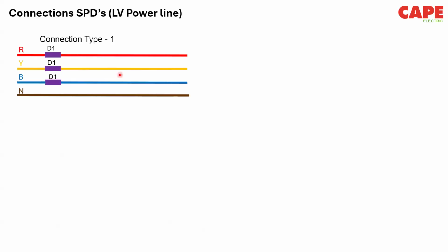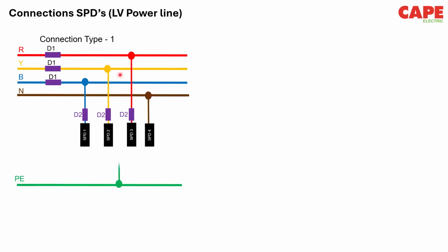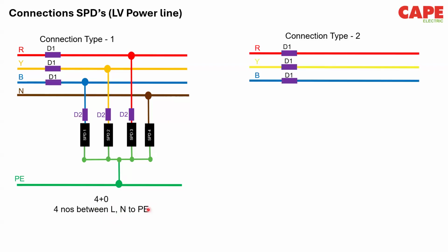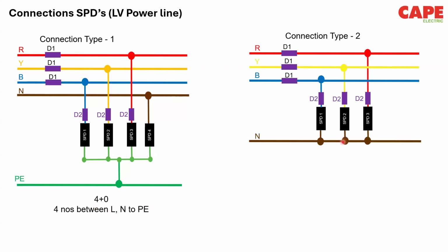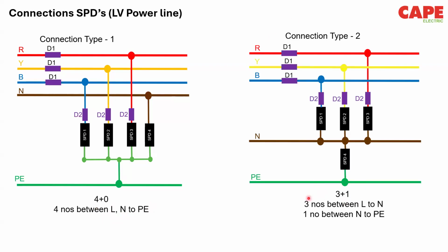Now, how do you install or select an SPD with respect to the power lines? There are two types of connections. In one connection, you have your power line and your earth conductor or PE conductor. This will be installed from each and every power line with respect to earth. So you can see here, there's an SPD connected to PE and with every phase and neutral with respect to PE. This is called a 4+0 connection. So there are 4 SPDs between line to earth, line and neutral to PE. Connection type 2, you have all the phases connected to neutral, and neutral is in turn connected to earth. This is called connection type 2, which is called 3+1 SPD. There are 3 SPDs between line to neutral and 1 SPD between neutral to PE.